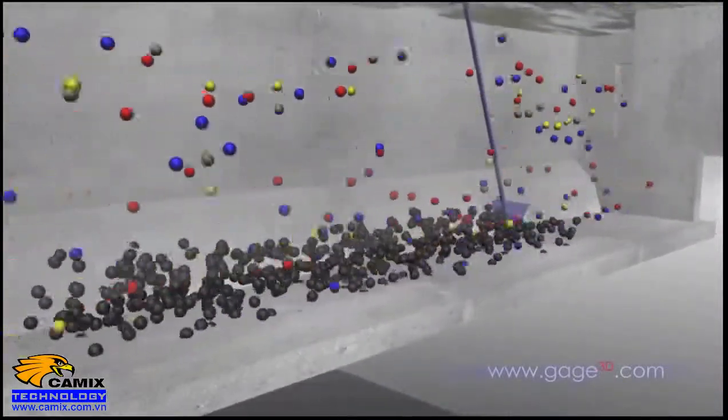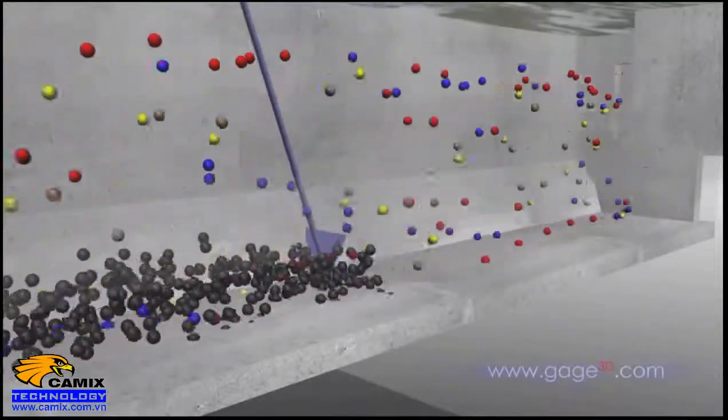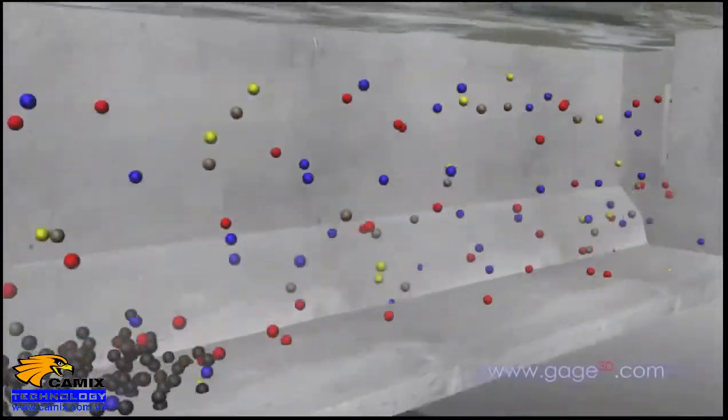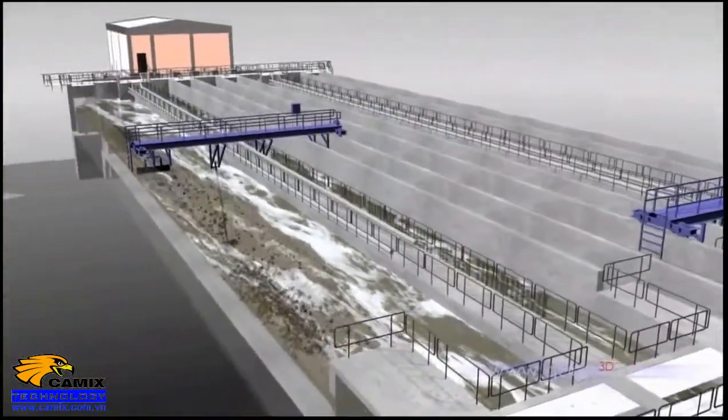As grit settles out, a rake runs along the bottom of the tank, sweeping the grit away. Removing grit early on is important because it is abrasive and can erode mechanical equipment. It can also build up in later treatment processes.